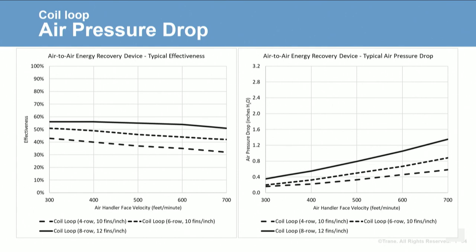The maximum face velocity in these charts is 700 feet per minute, but in a ductwork system the velocity could be two, three, or even four times that, impacting heat transfer and pressure drop. We also have to consider the water pressure drop of each coil: the 8-row coil has a water pressure drop of 19 feet of water, while the 4-row coil has only 10 feet. Each technology has a cost associated with energy recovery. For coil loops, there's both an air pressure drop and a water pressure drop, which are a function of the component and face velocity. Deeper coils may recover more energy but also increase fan energy and fluid pump power.